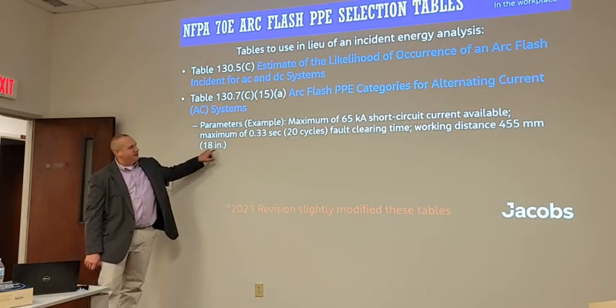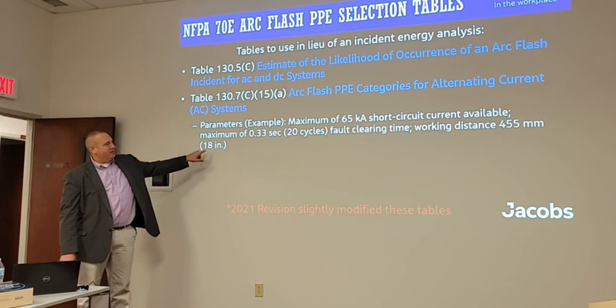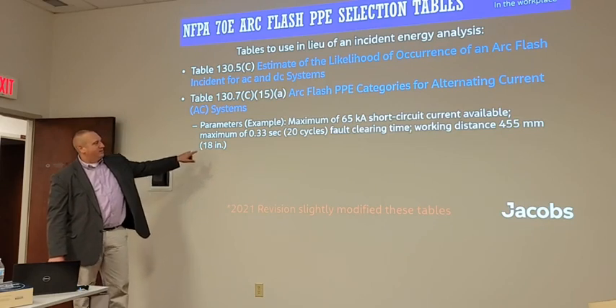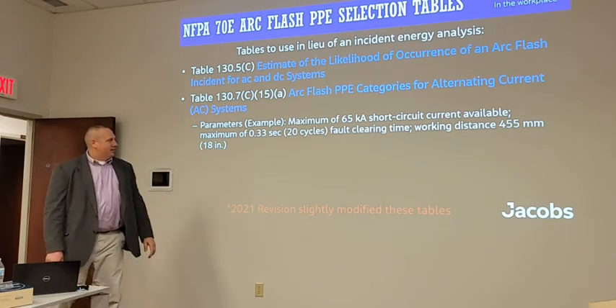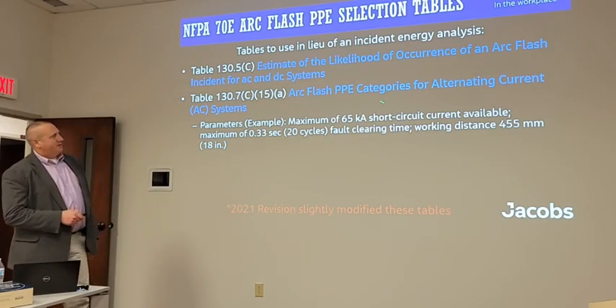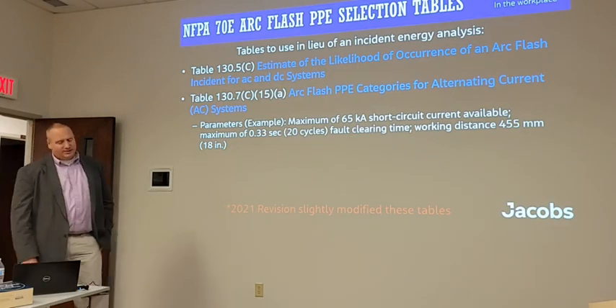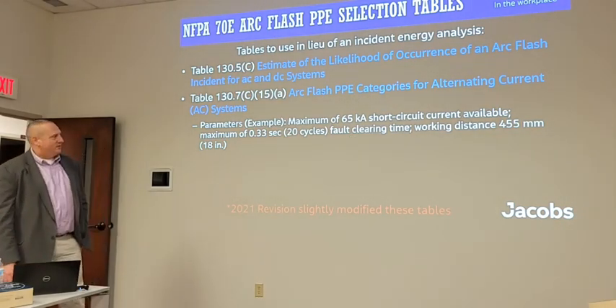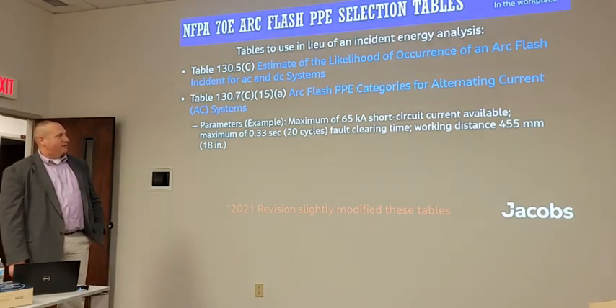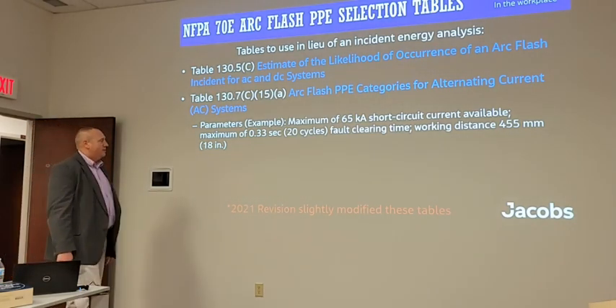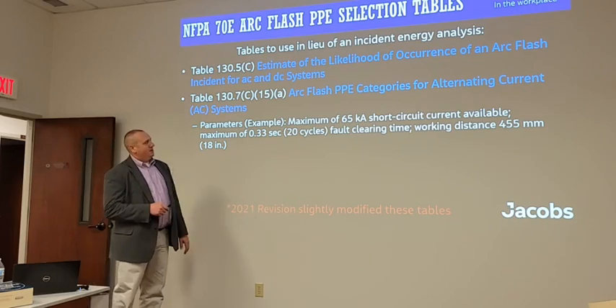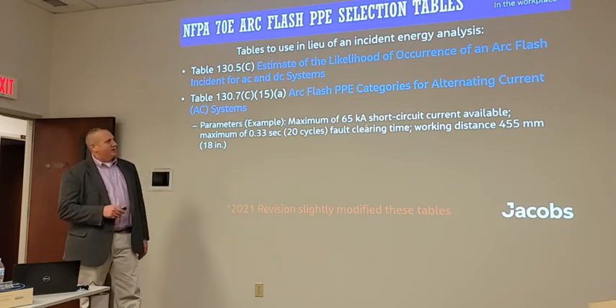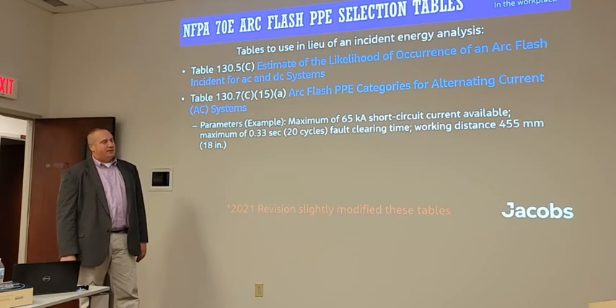This is an 18-inch working distance. I believe this would be a panel, maybe an MCC. But here we have a maximum of 65,000 amp short circuit current available and 20 cycles of fault clearing time. And then your working distance of 18 inches is taken out of the IEEE standard for calculating arc flash distance or energy levels. But what you need to know is, based on the equipment you're working on, is it rated for a maximum of 65,000 amp short circuit current?